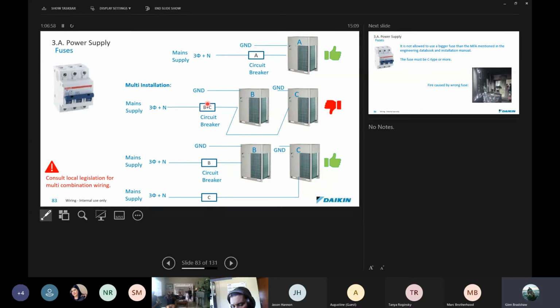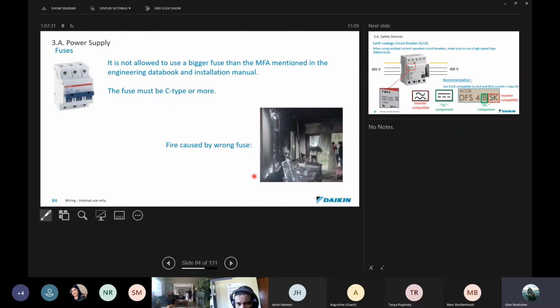that we actually had about a 50 volt drop across one of the phases. And this was just having a knock-on effect on PC boards that were being replaced in the unit. Once they separated the power supplies and put in new circuit breakers, never heard from the system again. So just consider that. You're not allowed to daisy chain power between units. Each system, as you see down here, must have its own three-phase and neutral and separate ground and separate circuit breaker and isolator for each system. So keep that in mind as well.